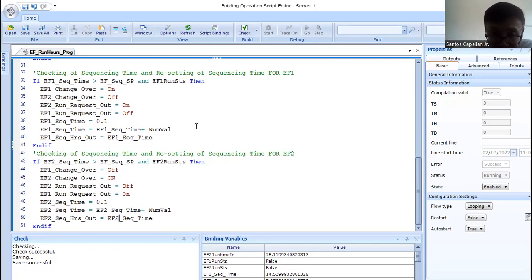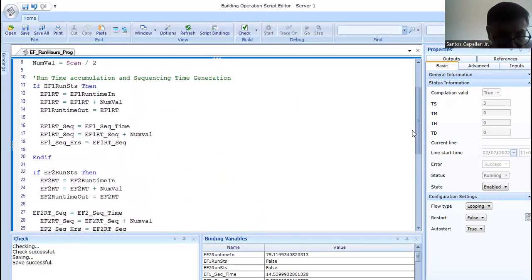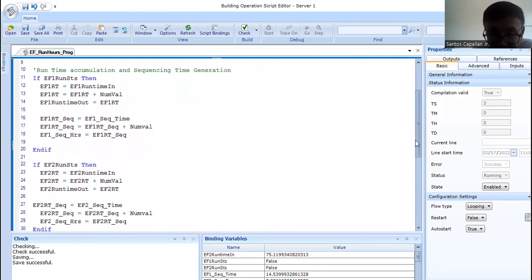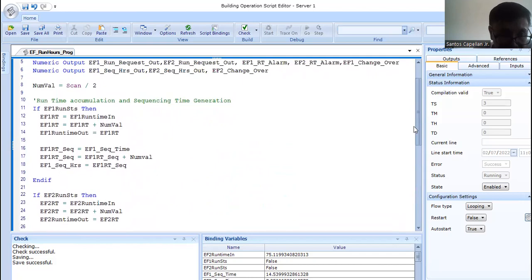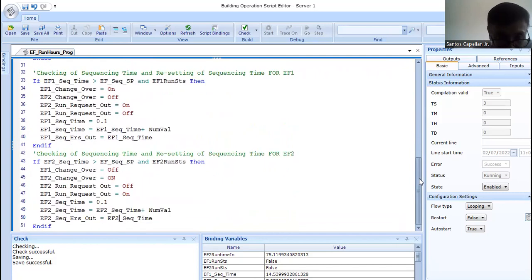This will just give an idea to beginners of how to do it. Maybe if the beginner engineer is a good programmer, then you can always edit this program and tailor it based on your sequence of operation. Once I finish this EF run hours program, I will try to make it more clean and neat — the script will be more readable. So this portion will be for EF1, and this will be for EF2. If EF1 sequence time is greater than the sequence set point — this is what I'm showing in my graphics.